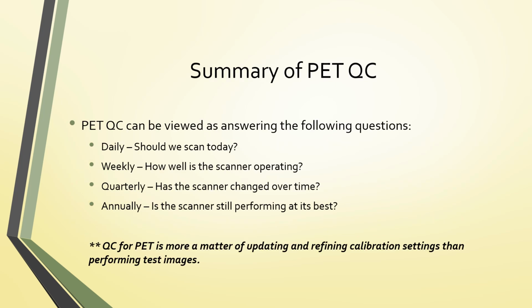PET-QC will vary per system. It also depends on whether it's standalone PET, PET-MR, or PET-CT system, and the manufacturer's recommendations. But the summary of the importance of PET-QC can be viewed by answering the following questions. For the daily QC, we want to answer, should we scan today? You just want to make sure that nothing has changed since the last time the scanner was used and that it's okay for use that day.